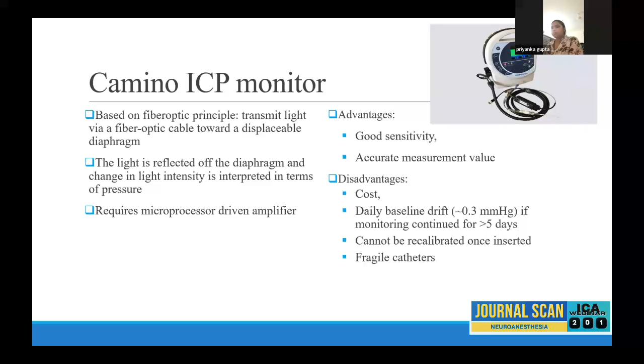A very good advantage of this type of monitoring is that they have good sensitivity and accuracy as compared to intraventricular, and they give a good estimation, near the intraventricular pressure. But the disadvantage is that because they are fiber optic cables, they are expensive. There is a daily drift of roughly 0.3 mm of Hg if it is used for more than 5 days. And once it is inserted, it cannot be recalibrated or re-zeroed again. Because they are fiber optic cables, they are fragile catheters and are likely to have fracture of the cables.